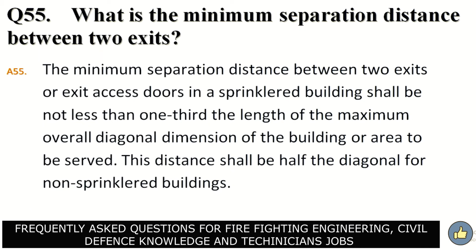What is the minimum separation distance between two exits? Answer. The minimum separation distance between two exits or exit access doors in a sprinklered building shall be not less than 1/3 the length of the maximum overall diagonal dimension of the building or area to be served. This distance shall be half the diagonal for non-sprinkler buildings.